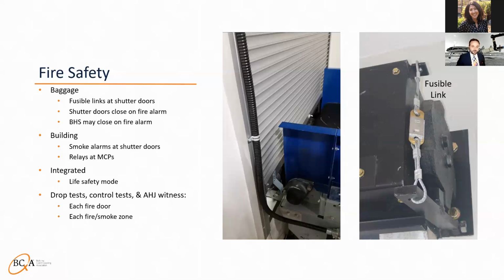Commissioning of this is a bit integrated in that the baggage handling system has to close under control in many ways. But often the authority having jurisdiction also will want to see bag doors close on fire alarms. This will be done with smoke alarm zone tests, sometimes using the smoke alarms at each door, or incrementally going through each of the fire and smoke zones in the building and ensuring the correct conveyor doors close. Also, you'll do a drop test where you pull a lever or otherwise activate or simulate activating the fusible link so that you can see that the doors fall shut on their own.